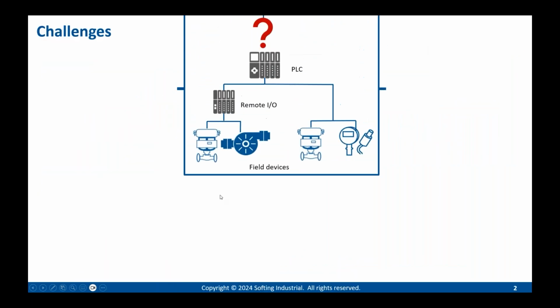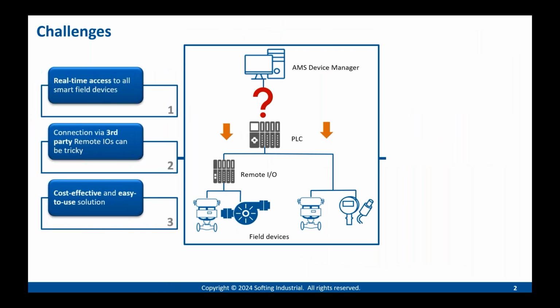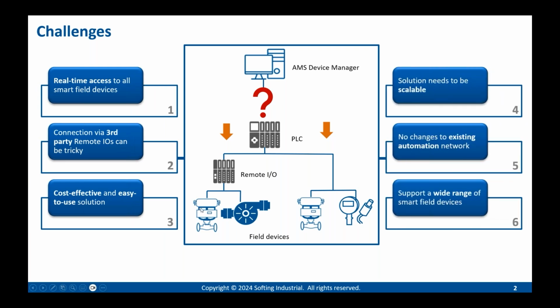Thank you once again, Konstantin, for highlighting all the challenges, and the main one is connection to third-party remote IOs. Let's look into the plant — how would it look? Here are different field devices that could be sensors, actuators, transmitters, valves, and you want to get the data out from these. They speak HART, connected to a remote I/O, and through a PLC you want to communicate to AMS Device Manager. So we want to move from preventive maintenance to predictive maintenance. As Konstantin said, whenever it's not the Emerson DCS system, it's really tough to get the data out. And whenever you go into a plant, the devices are not always from the same vendors, so I'd say one of the biggest challenges is that connection via third-party remote IOs can really be tricky.